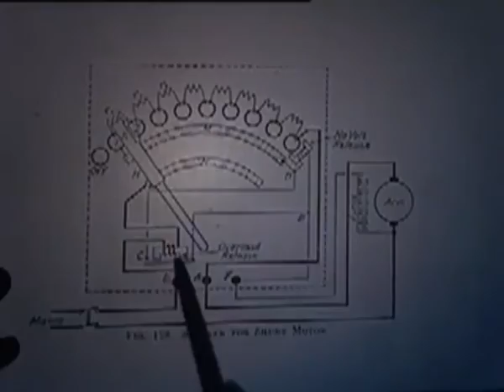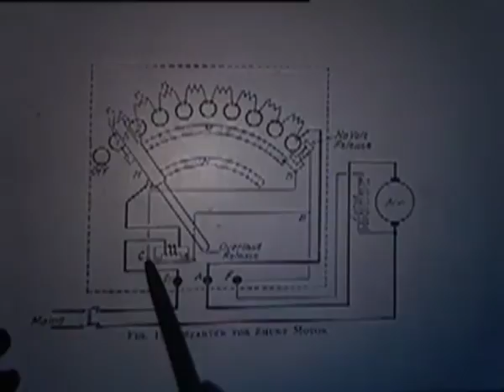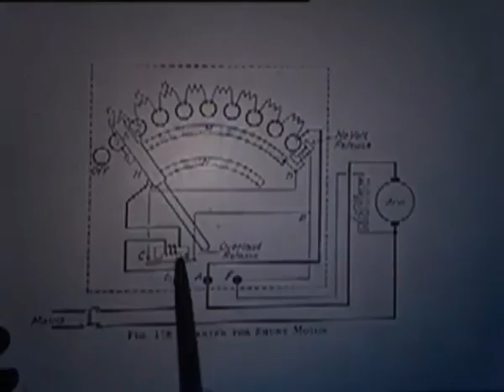Now while it continues to run, it also should protect the system. Whenever there are very high currents or overload, when very large currents are flowing, there is an electromagnet here that will short circuit these two points. This is called an overload release. With high currents above a threshold value, this will attract this and close this switch, so between these two, this is short circuited. When this is short circuited, there is no voltage across this, so it will automatically release the handle back to this position, because this gets de-energized with no current in this coil. So that is one way where this starter protects the machine.